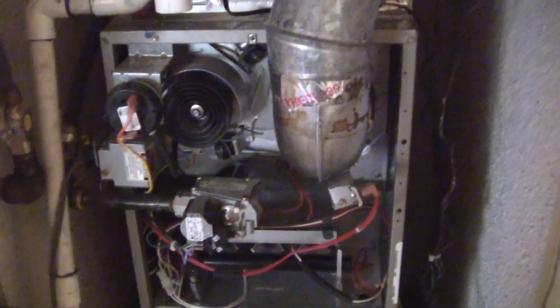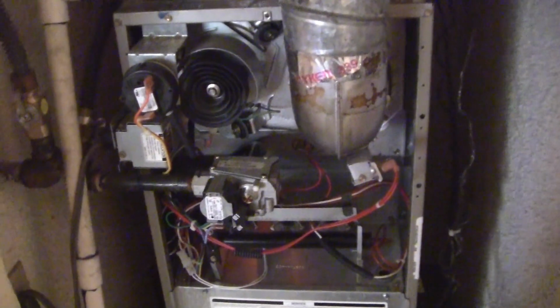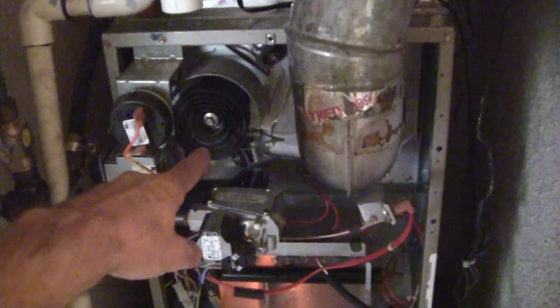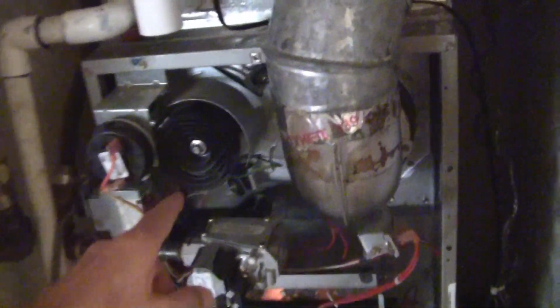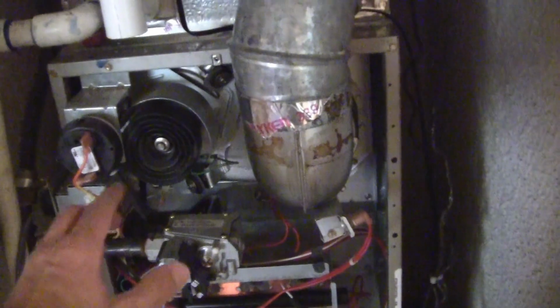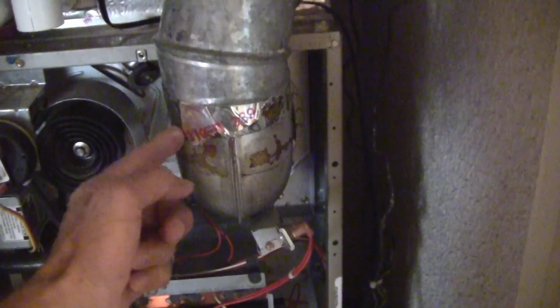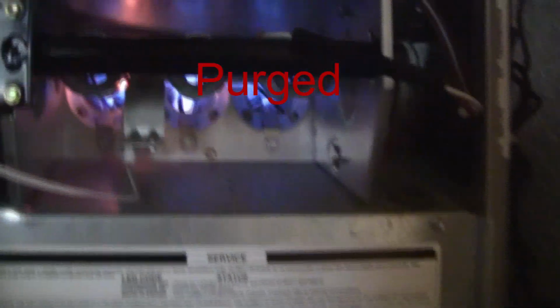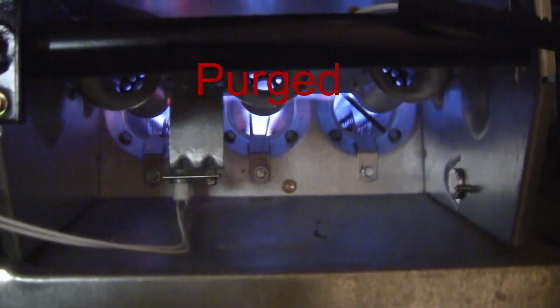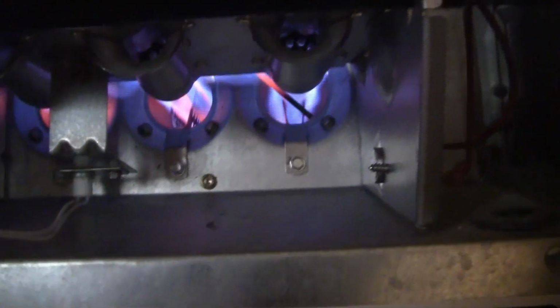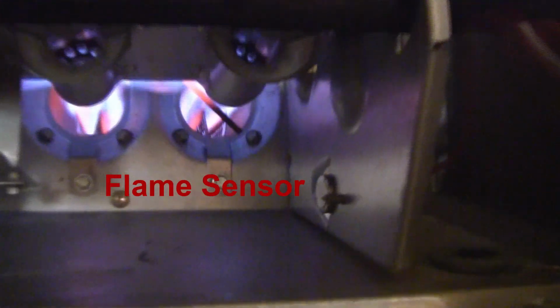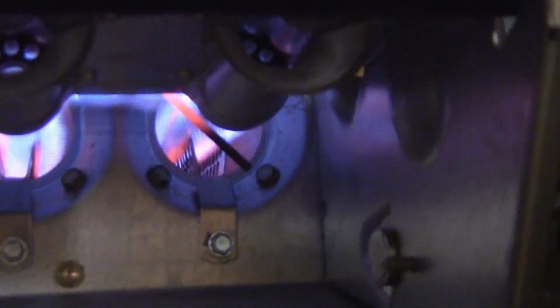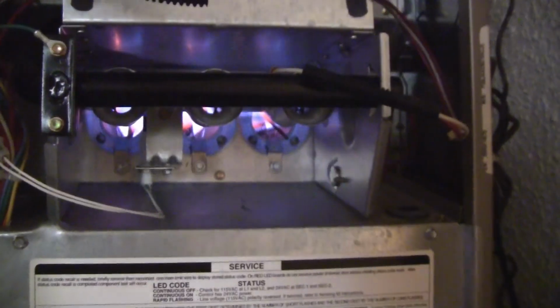Okay, so as a standard normal furnace sequence of operation, the first device that comes on is the inducer fan motor. The inducer fan motor is going to stay on for a certain time delay in an effort to make sure that the products of combustion are completely vented up. There we go. There's our gas. Boy, I just couldn't get down here fast enough. Okay, the furnace fired right up. Everything is fine. You can see the heat sensor right there. It's just off to the bottom side of that burner, and we're perfectly fine. I'm going to go ahead and shut the furnace off.